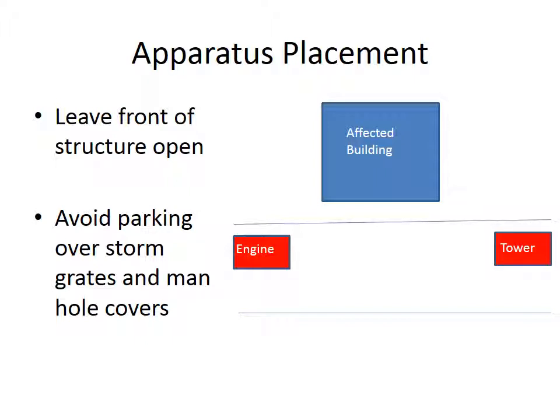And we want to avoid parking over storm grates and manhole covers. Storm grates, a lot of times if you have an outside underground leak, a migration type situation, that gas could be collecting in the storm drains. So we don't want to provide an ignition source by parking over the storm drains.